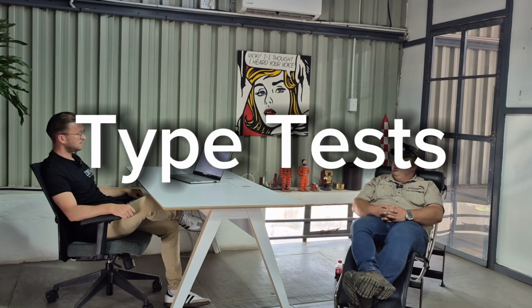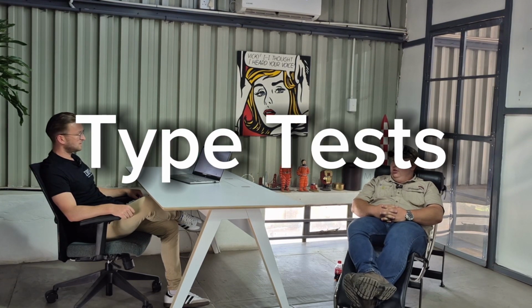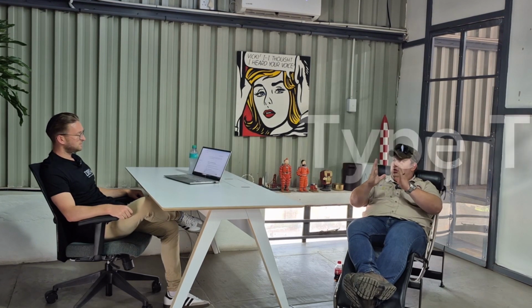It's a lot more difficult than just type testing. There's a lot more going into type testing than just type testing. Because if you type test on a certain range of amperages with a certain IP rating, with a certain kA fault level, then that is your type test. You can't use that again on a different board and say, but this one is also type tested, if you've only type tested on a certain level. That's correct. There's definitely a misconception about type tests.